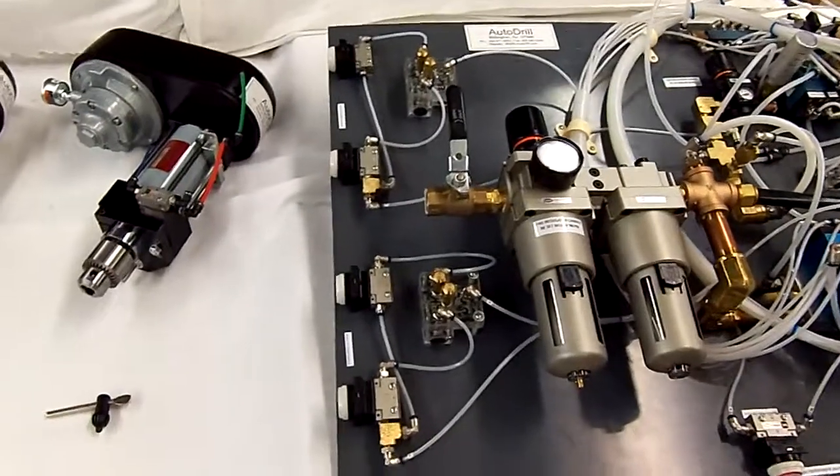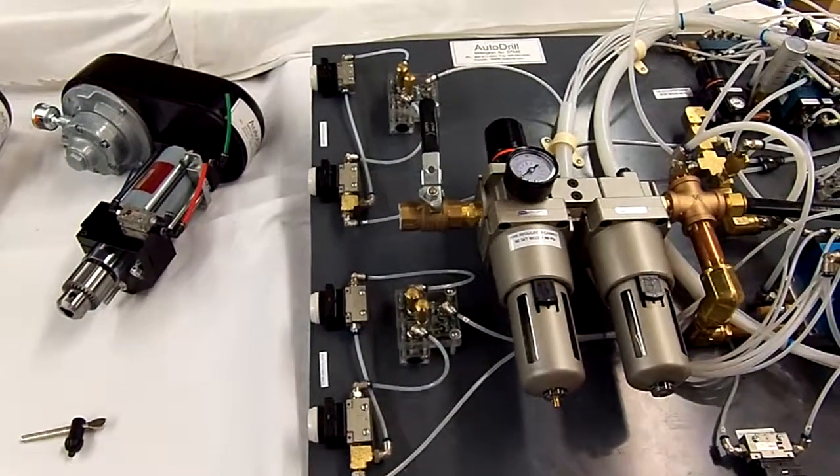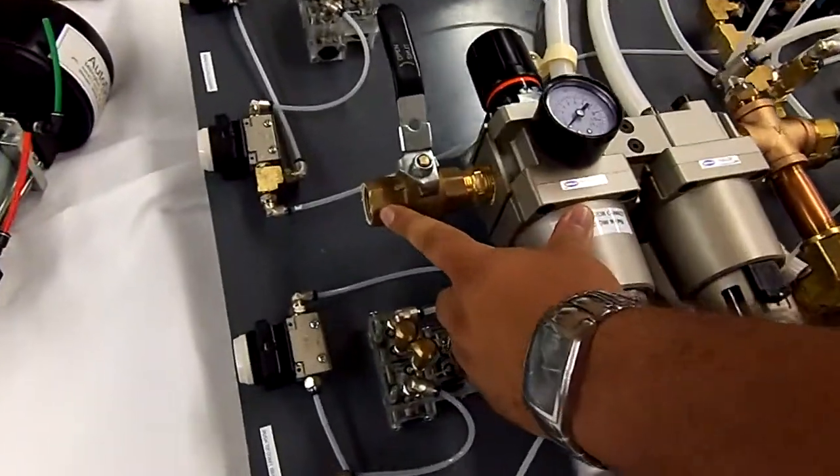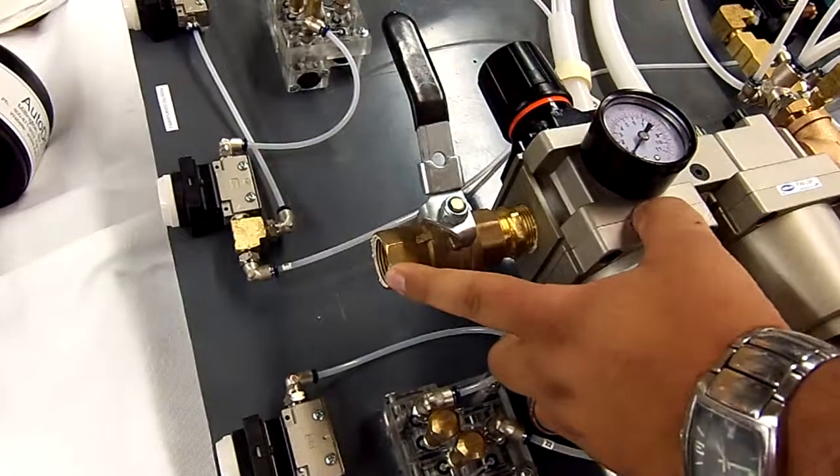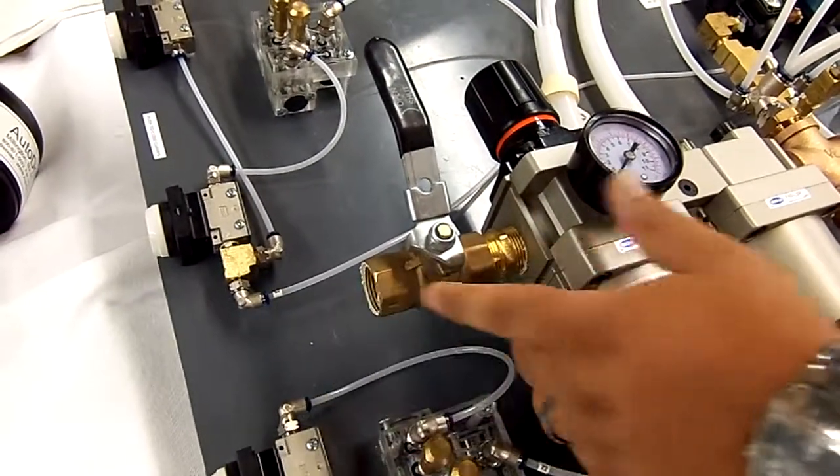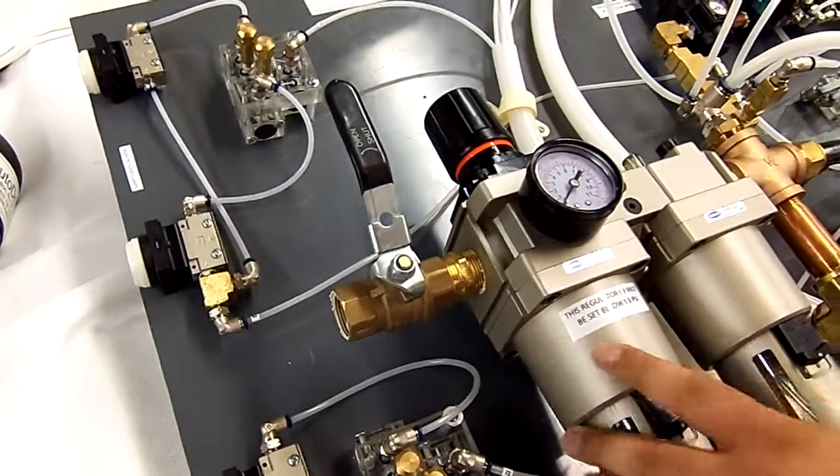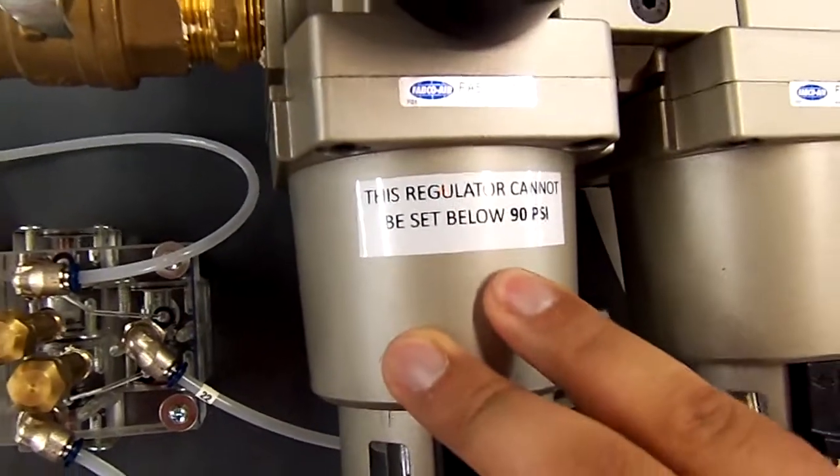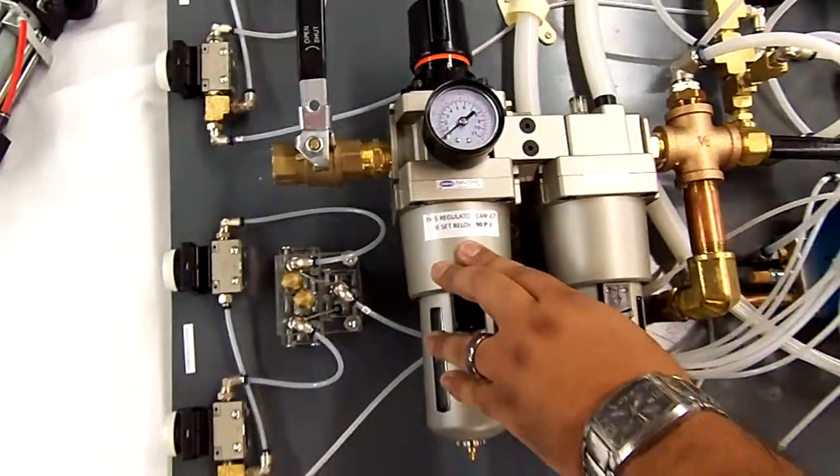This is a standard FRL with a dual manifold for controlling the operation of this drill. The input should be a 3-quarter inch or 1-inch tube. This is a 3-quarter MPT that runs into the main FRL. This label indicates that this FRL regulator cannot be set below 90 PSI.